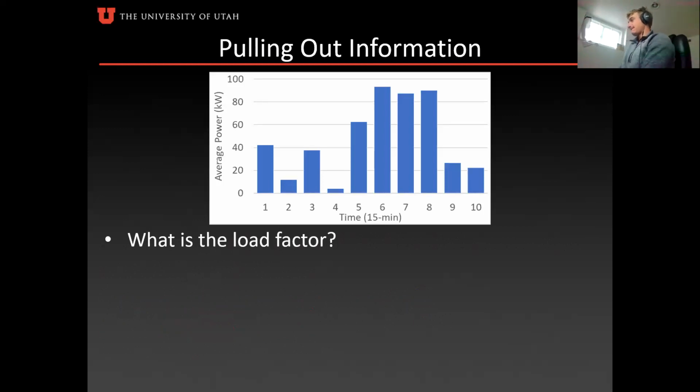So load factor, I like to think of it as how equivalent your demand use is. If you're using the same demand all the time, you would have a load factor of 1. The equation for that is the average demand divided by your peak demand.